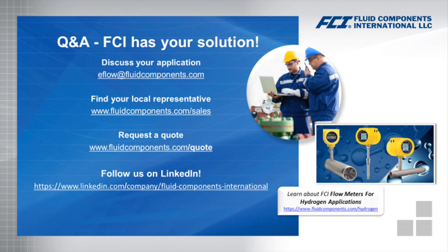What specification or standard governs the calibration of gas flow devices? Typically, there's several, but the more common ones you're going to see, and you might want to check with the manufacturer of any instrument, is: you'll see NIST traceability. You'll see reference to IEC, I believe it is 17025. Again, traceability on their calibration equipment. Make sure it's maintained properly. The primary flow measurement devices are kept up to date and calibrated because they need to be of much higher accuracy than the meter under test. Those are the two main ones we see as far as driving support of a manufacturer to ensure calibration of an instrument.